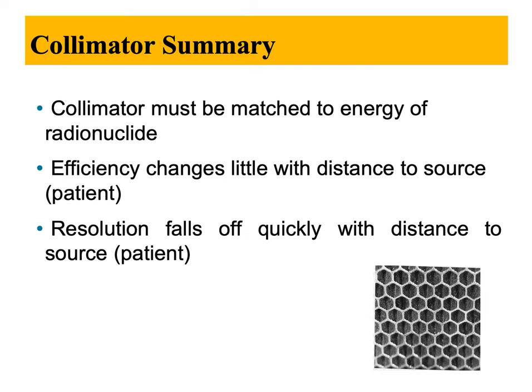In summary, the collimator must be matched to the energy of the radionuclide. Also, efficiency changes little with distance to source, while resolution falls off quickly with distance to source. We need to keep these in mind when designing gamma cameras for nuclear medicine imaging. Thank you for watching, and until next video, bye.